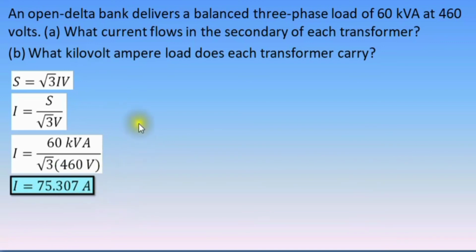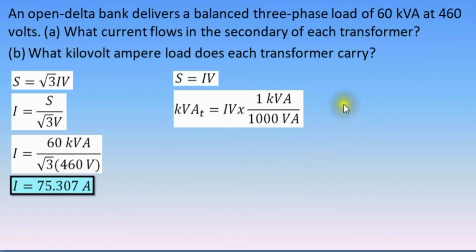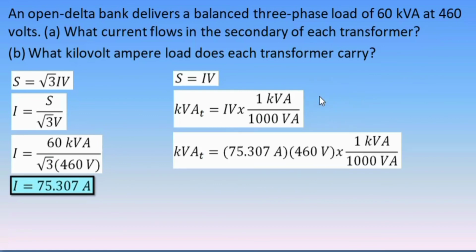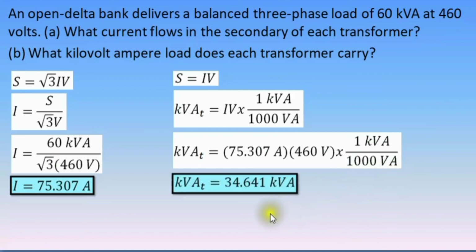Now let's go to letter B, the kVA load of each transformer. That is simply current times voltage because we are solving for the kVA load of each transformer. Current equals 75.307 amperes and the voltage is 460 volts. But of course, we need to convert that into kVA. So we have 75.307 amperes times 460 volts times 1 kVA over 1000 volt amperes. The answer is 34.641 kVA.